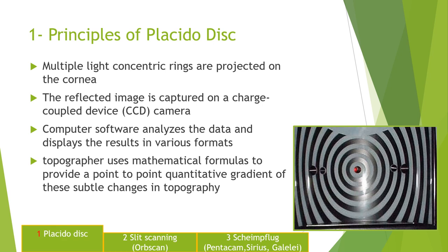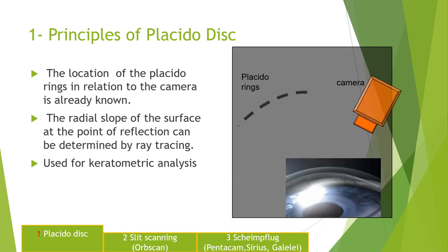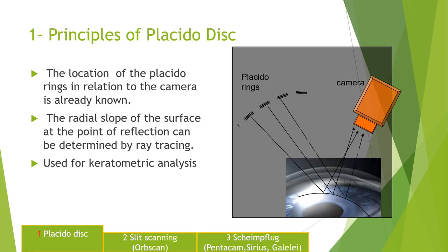Placido disk: you have multiple concentric light rings which are projected onto the cornea and from there you analyze the shape of the cornea. The Placido rings are reflected from the cornea and captured by the camera, and that's how the camera analyzes the topography. Remember, it only gives you the topography — it doesn't give you the tomography. So you only study the surface of the cornea, not the cross section or the depth of the cornea.